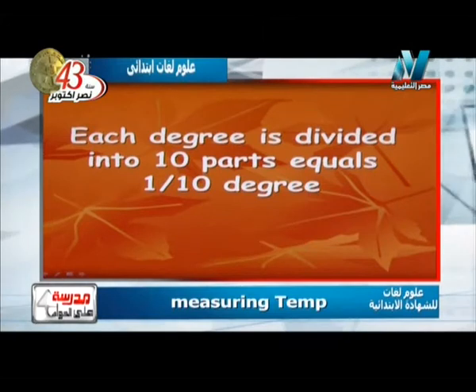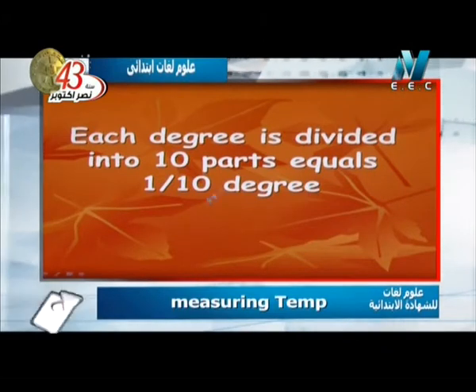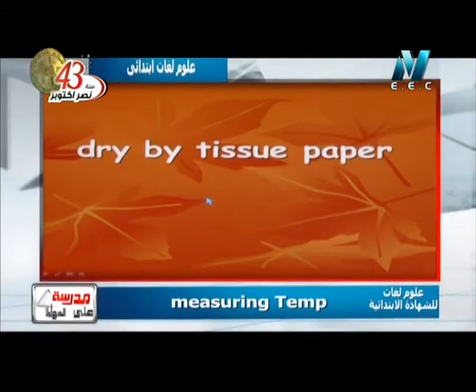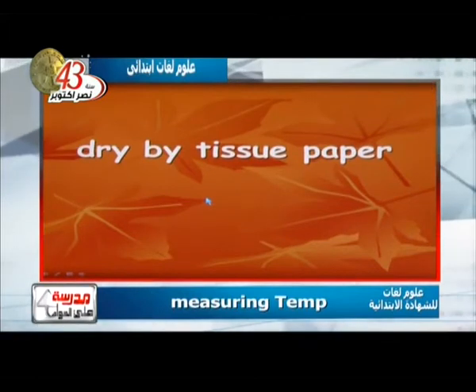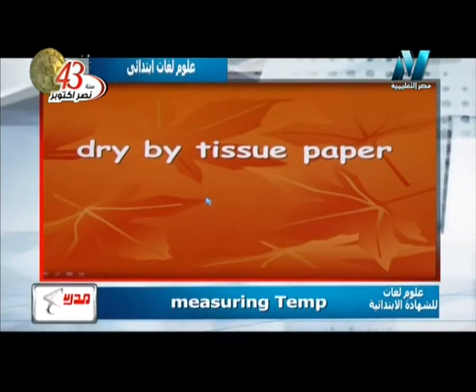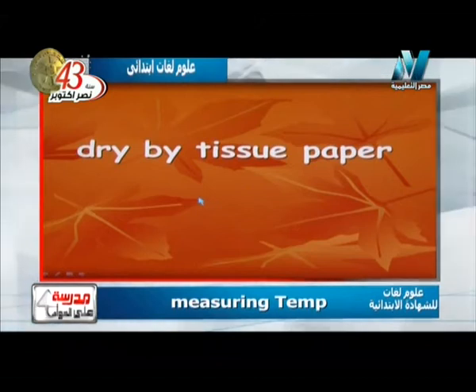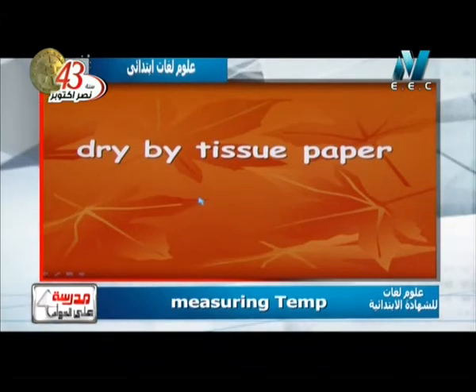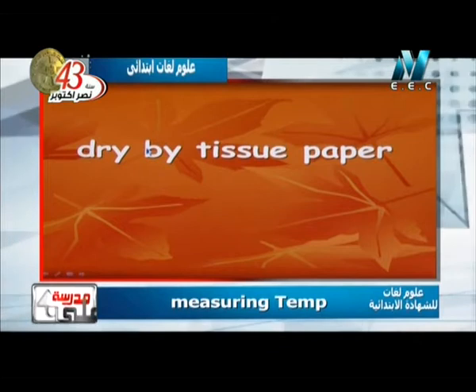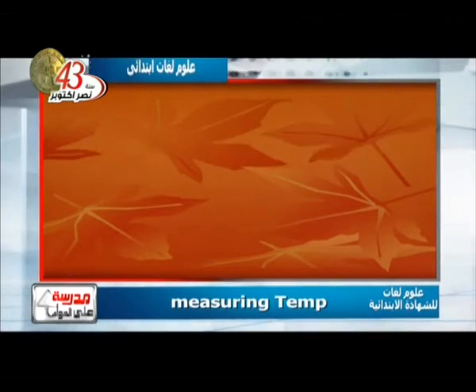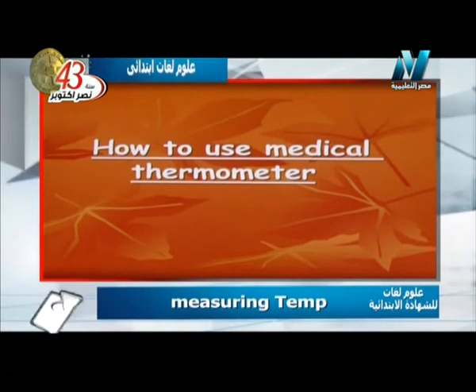So it's very accurate than the other thermometer. Another information about the medical thermometer. We must dry it by tissue paper after using or before using because we use alcohol. Alcohol, you know, alcohol or ethyl alcohol or any perfume to sterilize the thermometer, okay? So now, how to use the medical thermometer?